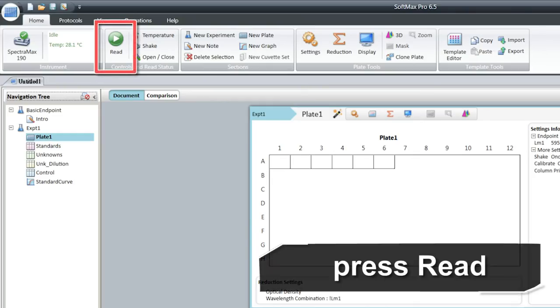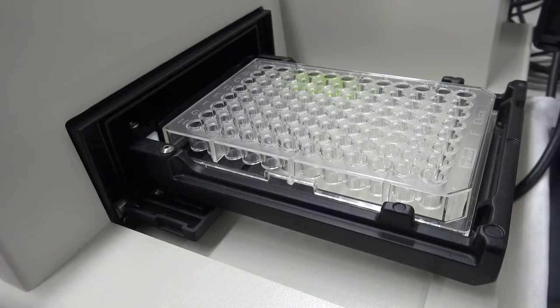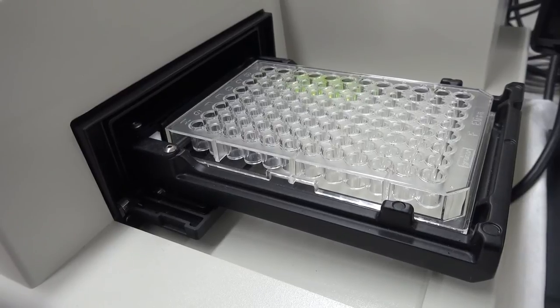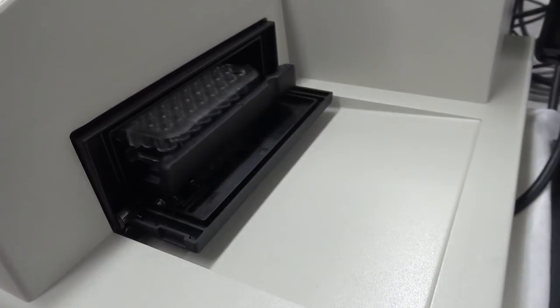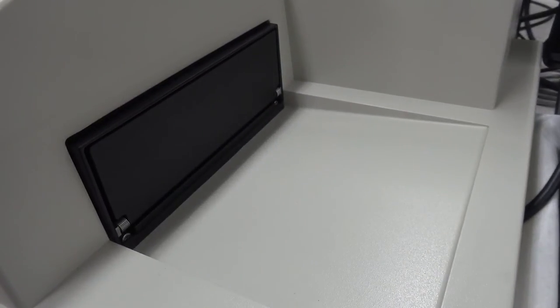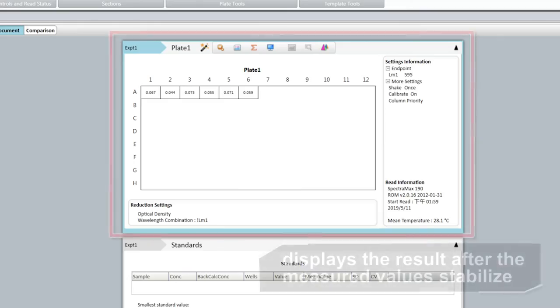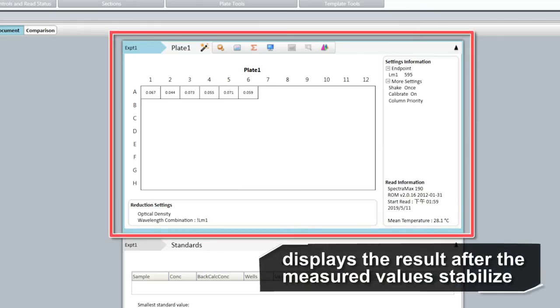5. Next, press read in control software. 6. The spectrophotometer takes in the microplate automatically and shakes it a few times before measuring. The computer screen displays the result after the measured values stabilize.